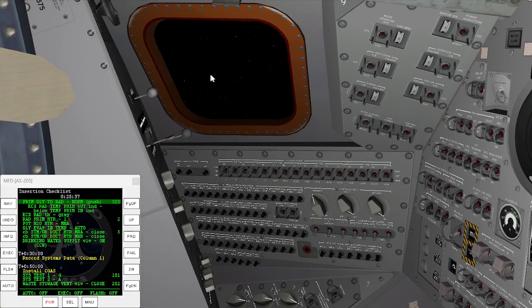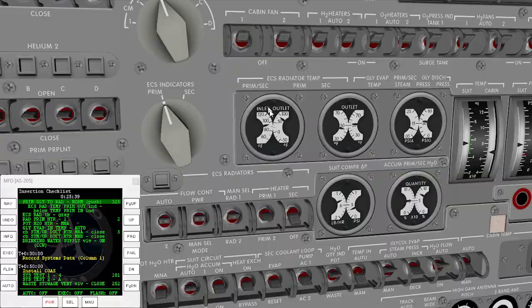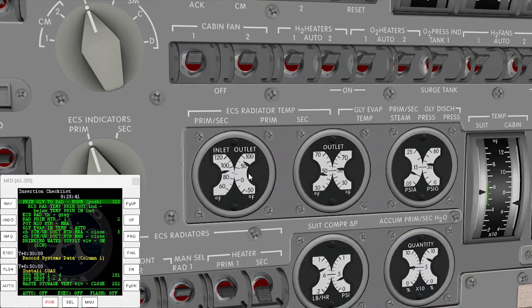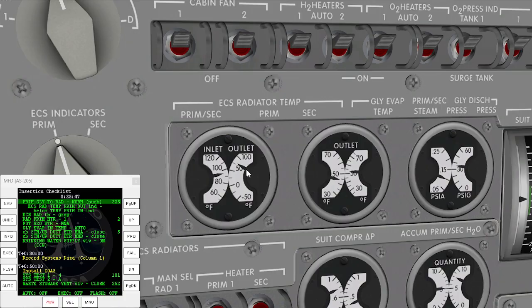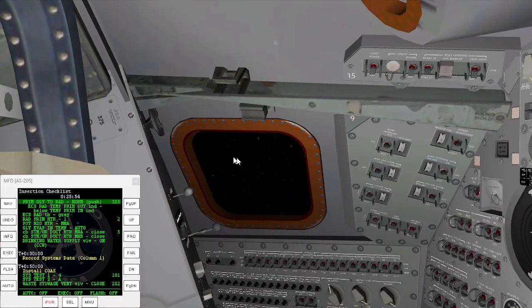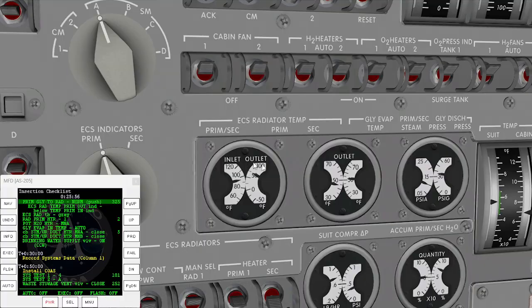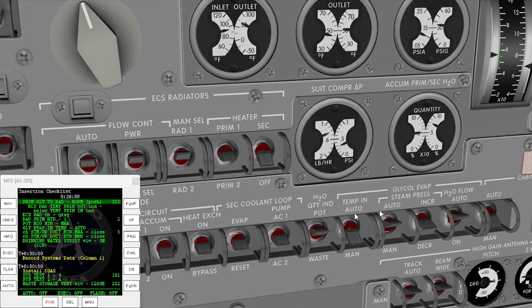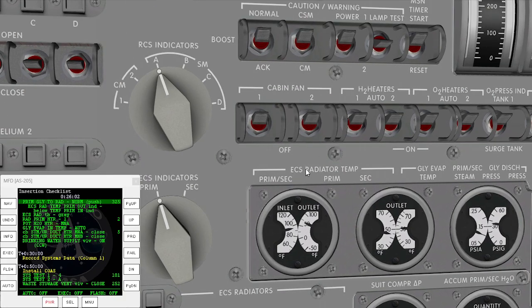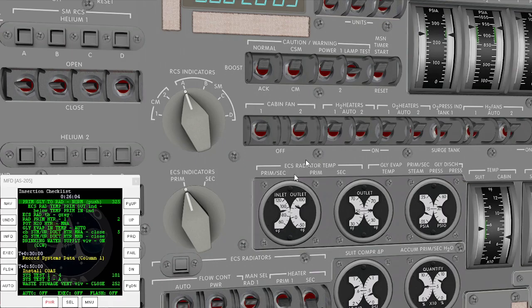And we're going to push. The radiator primary outlet should be below the primary inlet temperature, and we can see that is very much the case. If this was not the case, we would have to bypass the radiators again and keep cooling with the active system before starting flow through the radiators again, or we could risk damaging the system.